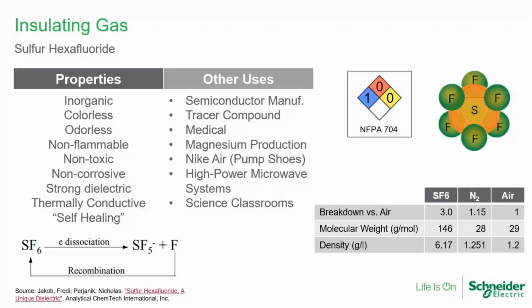In the medium voltage range, while that's hard to escape in the high voltage world, in the medium voltage world it's very easy for us to provide SF6 switchgear that doesn't require any SF6 handling on site, doesn't require either draining or refilling tanks for maintenance procedures. So when you're considering using gas insulated switchgear, I think it's important to consider switchgear that is SF6 filled at the factory and doesn't require any on-site managing of gas.